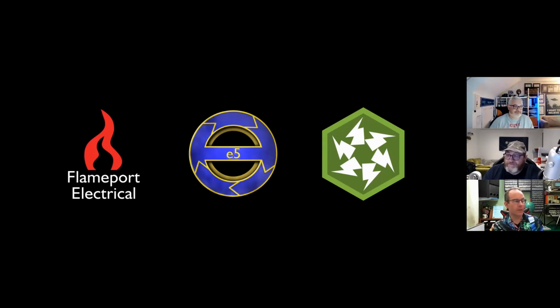So yeah, all TT systems do have a connection between neutral and earth. It's just where it is: back at the supply, or if you're in island mode, it could be within your own installation. And the third one, which I just had a look to see what the wording actually states: when in island mode, does the supply's earth have to be disconnected as well as the live conductors? It doesn't say that that's actually the case.